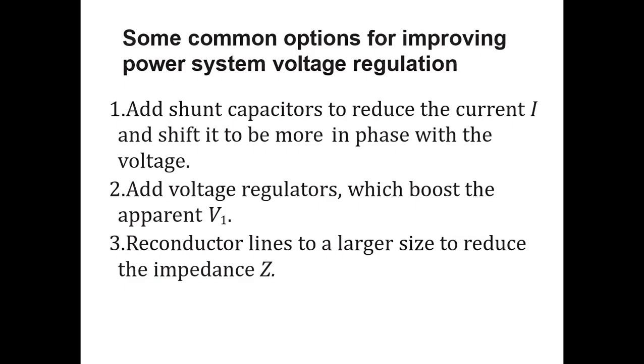Now, some common options for improving the power system voltage regulation. Keep in mind what the meaning of voltage regulation is, what its ideal value is, and what precautions we need to take so that we can regulate the voltage or improve the voltage regulation. First of all, voltage regulation is the change in terminal voltage from no load to full load, divided by no load, multiplied by 100, which gives the percentage regulation. Ideally, our requirement is that whatever load you connect to the power system, even if you connect a changing or varying load, the voltage should be constant.